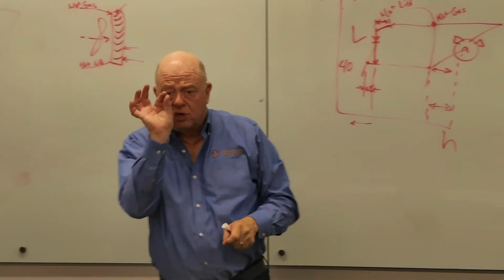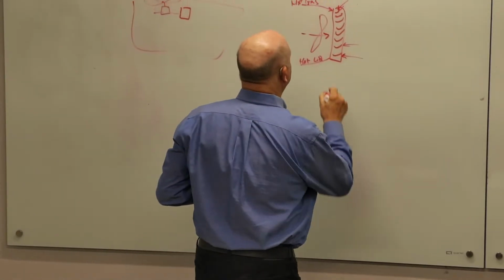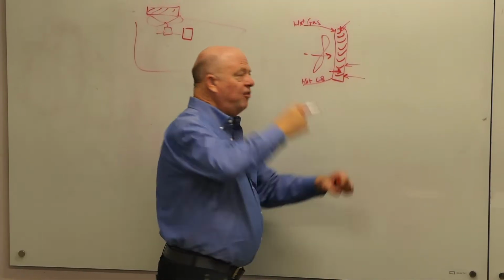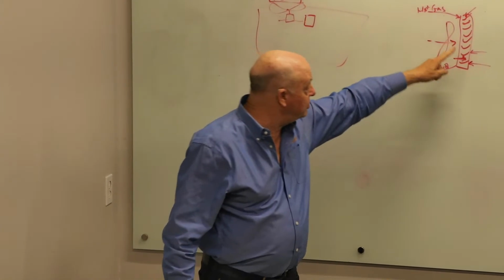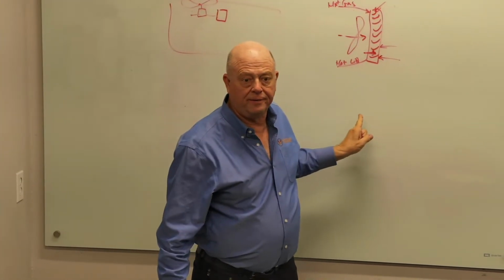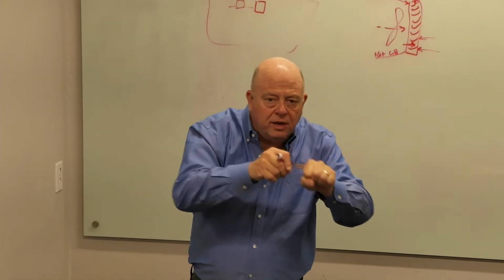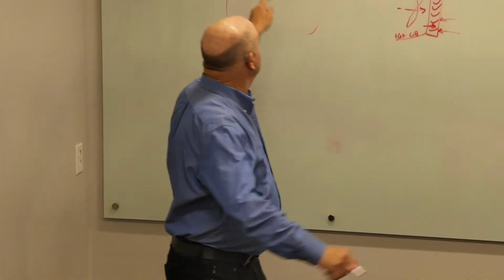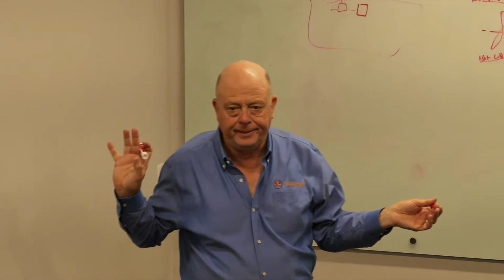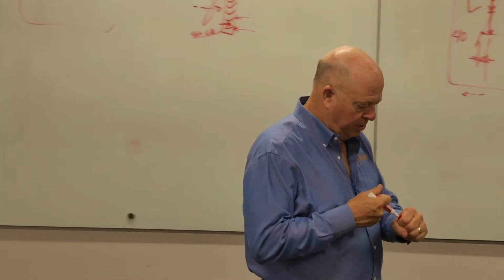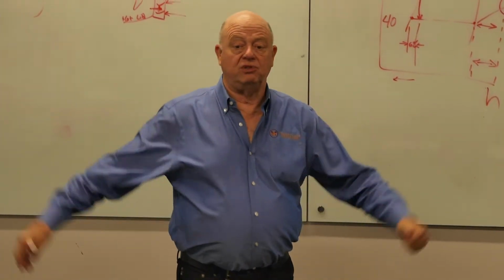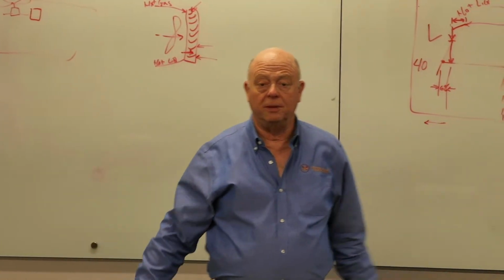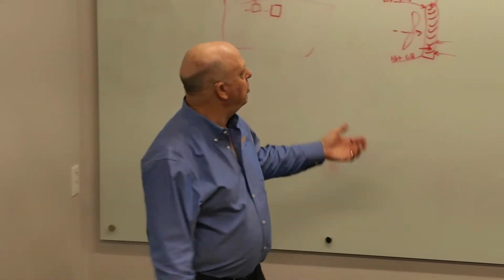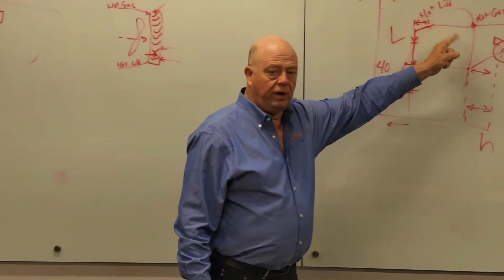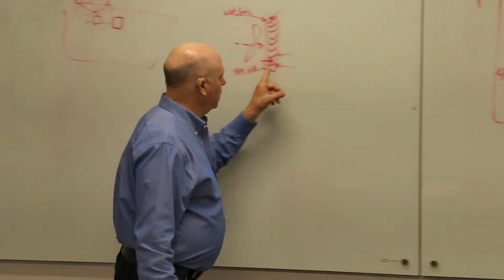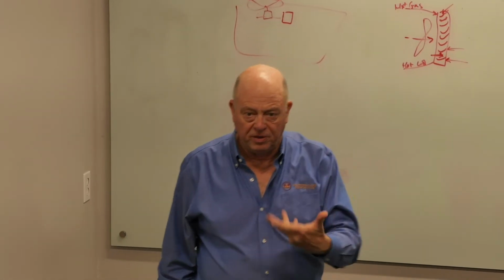And the way it was controlled, there was a temperature sensor. You stuck that temperature sensor into the coil fins down here before it left, because remember, this is the coolest spot. This is seeing the subcooling down here at the bottom. That's where you jammed in the temperature sensor, which would then slow the fan motor down so you wouldn't reject so much heat. This general principle is how we do it today. If you've got some big system we built up, we probably provide a variable speed drive, and we probably either monitor the pressure here, which is the better way to do it, or we look at the temperature of the fluid leaving, but the pressure would be the preferred way.